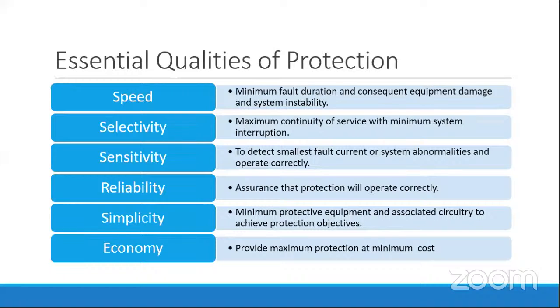Now, essential qualities. The essential qualities for protection are speed, selectivity, sensitivity, reliability, simplicity, and economy. Speed means the fault should be isolated from the system as soon as possible, so that equipment can be saved from getting damaged and we can keep the system from becoming unstable. So we need to ensure that the switch gears installed for protection operate in minimum time, so that our equipment does not get damaged.